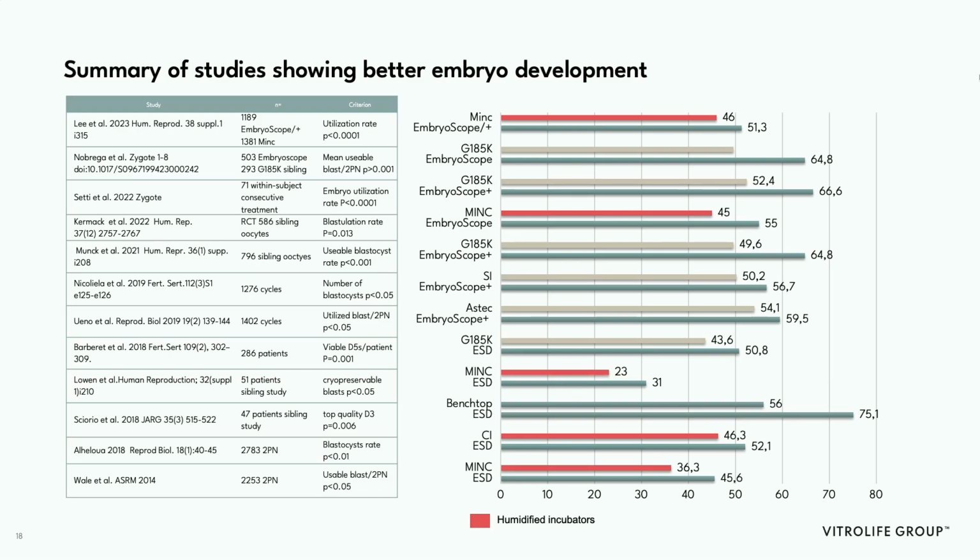But the real truth in humidified versus non-humidified is looking at the embryo development. And if you're not reporting actual embryo development, you're not learning anything. So you can't just say dry, non-humidified. We have very many studies showing excellent embryo culture in our system, with our dish type and our oil level, and comparing to both humidified and non-humidified incubators.